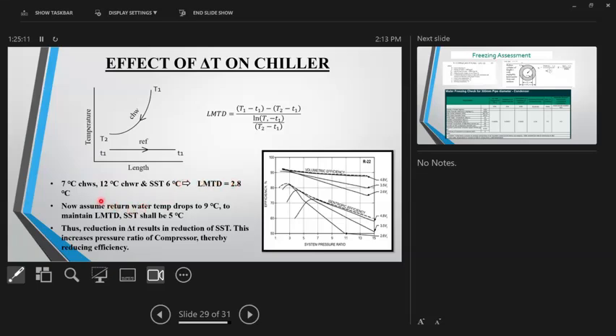Now, instead of 12 degree return, you are having only 9 degrees. So delta T has reduced from 5 to 2 degrees centigrade, right? So this is the low delta T syndrome. So your return water temperature is 9, and so instead of 12, it is 9.